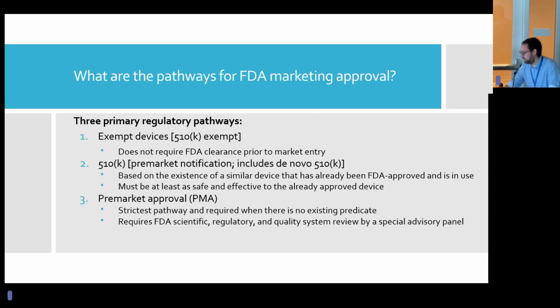And this is the strictest pathway. This is for all class 3s. Essentially, some class 2s will fall into this category as well. This is the most stringent pathway. If there's no existing predicate, or even if there is an existing predicate, you still have to go through this pathway. It requires contact with the FDA pretty early in the process. You need to have scientific data and regulatory quality systems. This is all approved, and so, again, it takes a longer path. We'll talk a little bit about costs and pathways and how long it takes in general. But from concept to an FDA PMA approval can take as long as 3, 4, 5 years. So it can take a while.